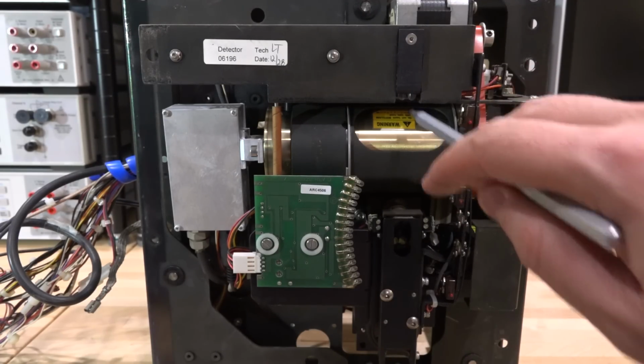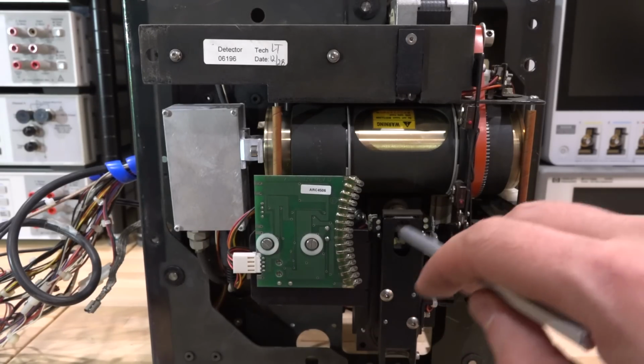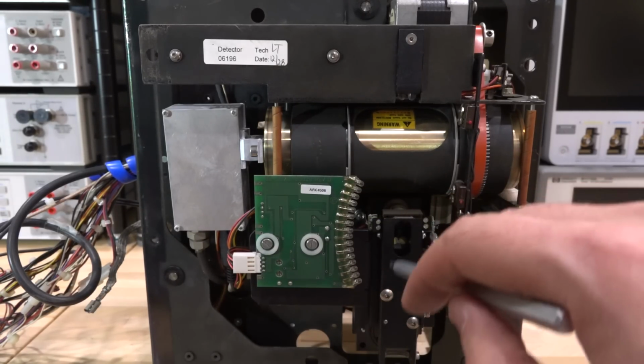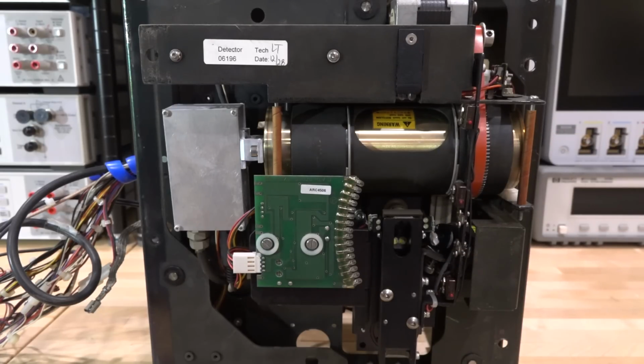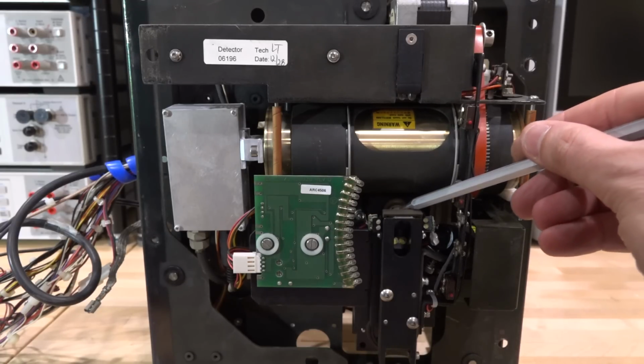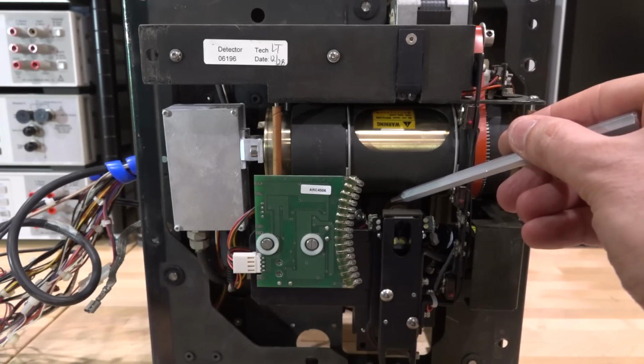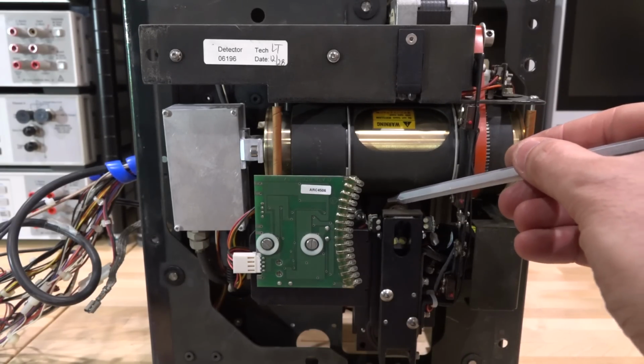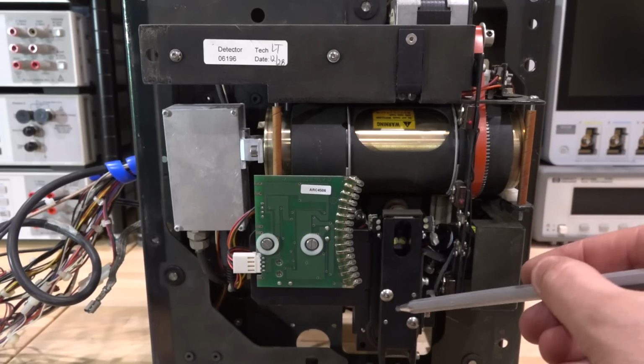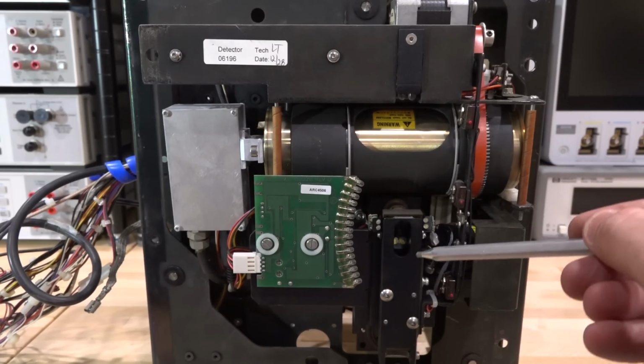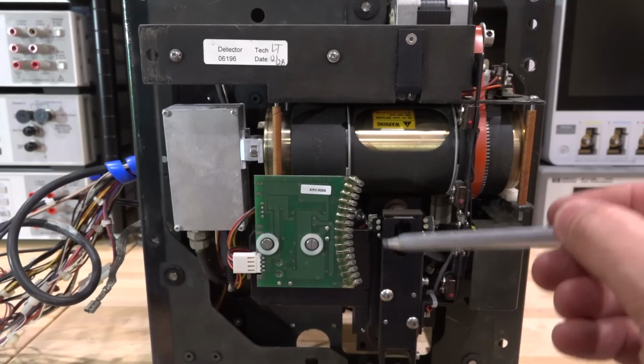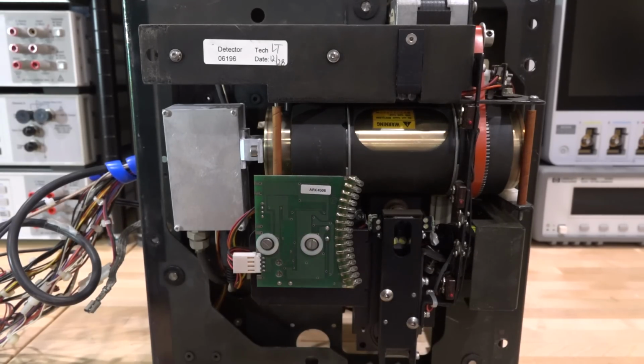There's even 2 over here, and there's a couple in here that are pointing directly into the sample. This could just be for lighting, so the camera can see what it's looking at. So the camera's opening is over here, hard to see at the bottom, but there's a mirror in here, and it reflects off of this, and it looks at the sample. So if you put a sample over here, the camera can see it. At the same time, this thing over here is the opening aperture of the X-ray, and that goes through the mirror too, which is kind of funny. So the point of the X-ray and the camera look at exactly the same place, which is what you want, because you're trying to sample what it is that you're exactly looking at. It's a pretty interesting design.